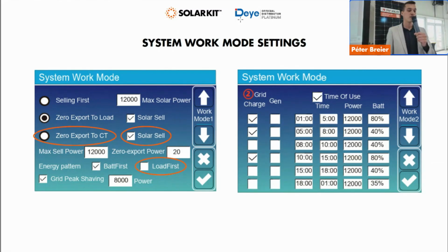Other than that, you can raise the 0 export power. That one is for the 0 inject reserve. So basically that amount of power will also always be taken from the grid. So when you turn off a consumer, it will have some time to regulate the inverter AC output, so it will not inject anything back into the grid. If you have big consumers on the side, then you can raise this power to like 40 or 80 watts, and you will see that it will not inject back anything into the grid. Otherwise, it can sometimes, when you switch off the consumers, add a little bit back to the grid. I believe for most competitors, this is also around 20, 30, sometimes 50 watts, dependent on the brand.